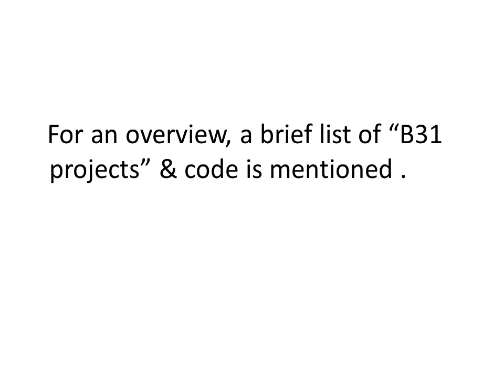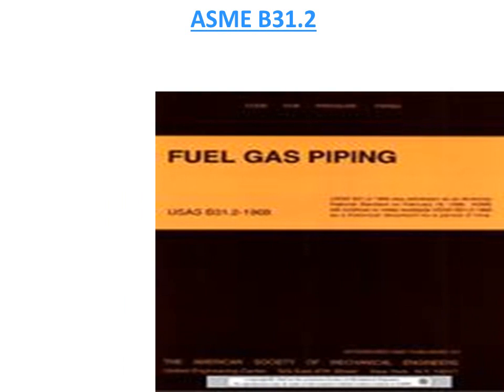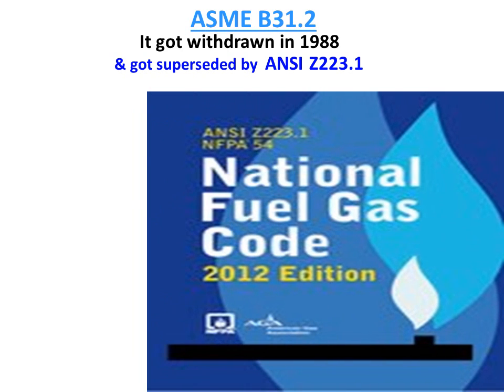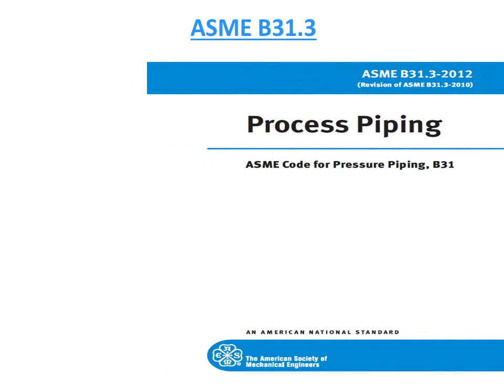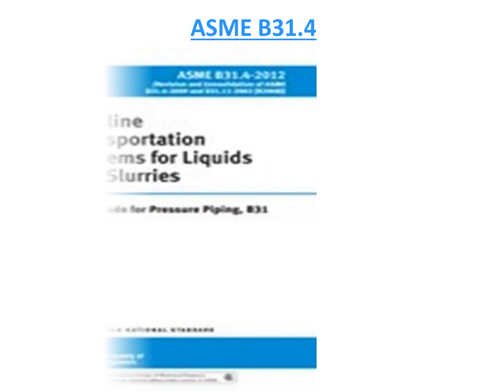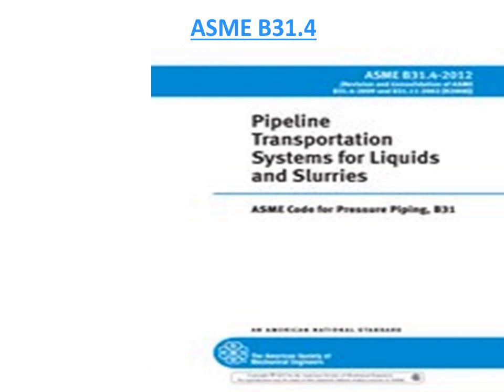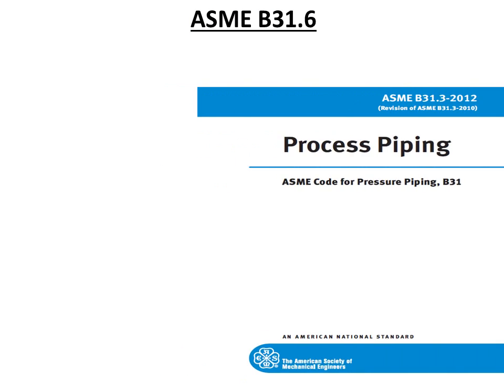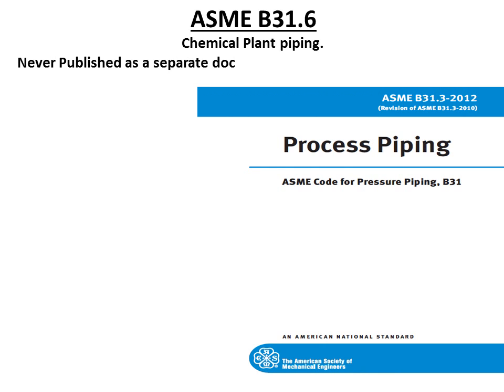For an overview, a brief list of B31 projects and codes: ASME B31.1 is for power piping. ASME B31.2 was meant for fuel gas piping but was withdrawn in 1988 and superseded by ANSI Z223.1, the National Fuel Gas Code. ASME B31.3 is for process piping. ASME B31.4 is for pipeline transportation systems for liquids and slurries. ASME B31.5 is for refrigeration piping and heat transfer components. ASME B31.6 was meant for chemical plant piping but was never published as a separate document and was pulled into B31.3 itself.